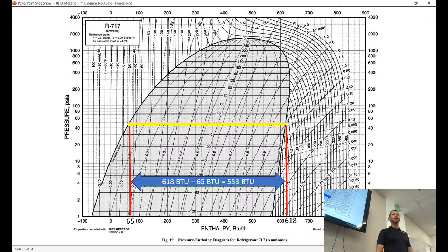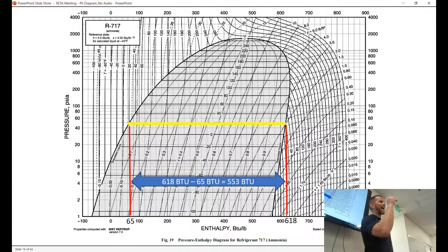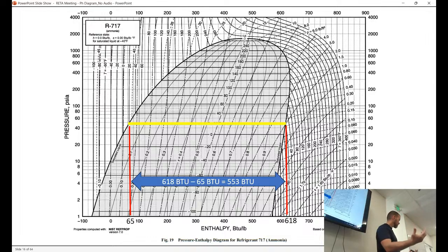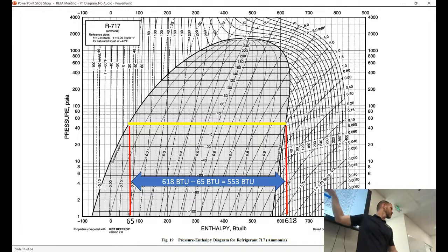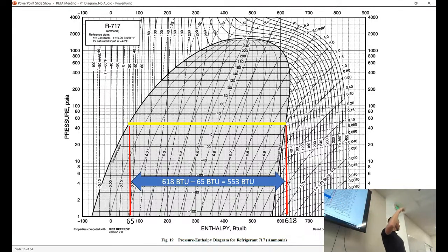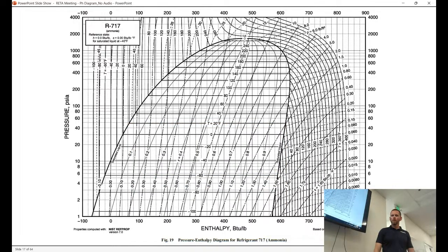If I go all the way to become a saturated vapor, that corresponds to 618 BTUs. This difference — 618 minus 65 — is 553 BTUs. That is the latent heat of vaporization of ammonia at 20 degrees. If you've taken the CARO exam, you probably had to memorize the latent heat of vaporization of water: 970 BTUs per pound. But what that fails to recognize is that's at a specific condition — at sea level, 14.7 PSIA, zero gauge. The latent heat of vaporization actually changes — as you get to the top of the curve, it becomes much smaller. So latent heat of vaporization is not just one number.